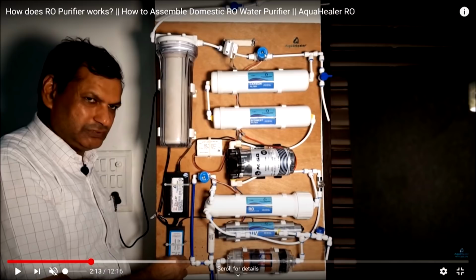And then it goes through different solenoid valves, but we are not going to talk about all these aspects. Then we see that it goes to a carbon filter, then to a sediment filter. Carbon meaning activated carbon, where you adsorb the organics, and then a sediment filter, typically sand or such, sand filtration, and then to a pump. We will see why. Why do we need the pump here? Because we have an RO unit here, a reverse osmosis unit, which requires high pressures.